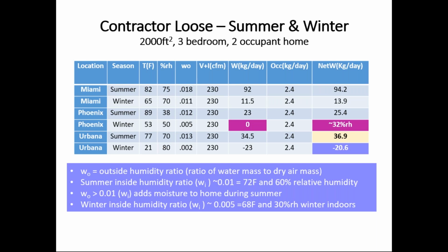The winter in Phoenix, with 0.005 or 0.5% water in the outside air, when that blows through, that's helping to dehumidify or pull down the moisture generation of the indoor occupant activities. And so by not humidifying, using that same relation that we showed before, you can instead turn that around and figure out the humidity. The relative humidity in this case would be about 32% in this home, this leaky home, during the winter. And in Urbana, you would add about 20 liters of water into the air in order to try to keep it at about 30% humidity.